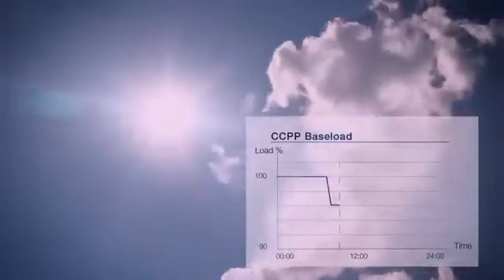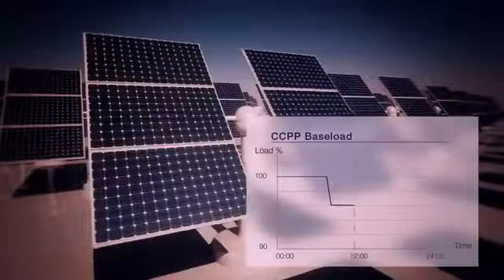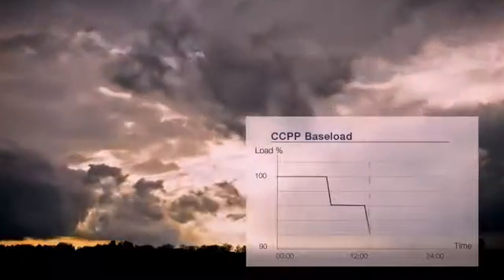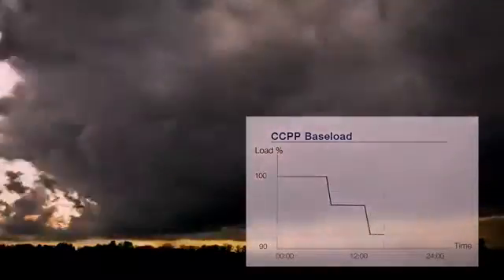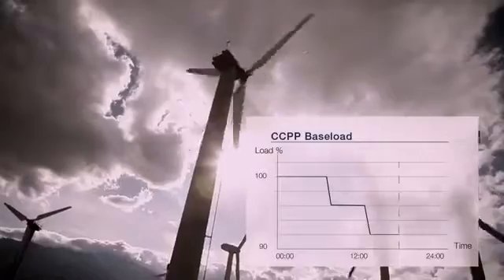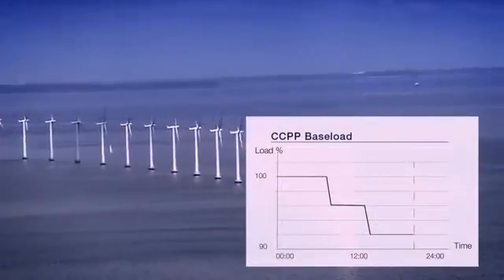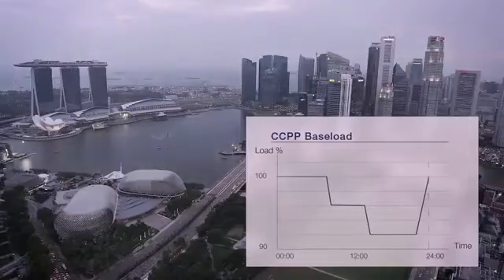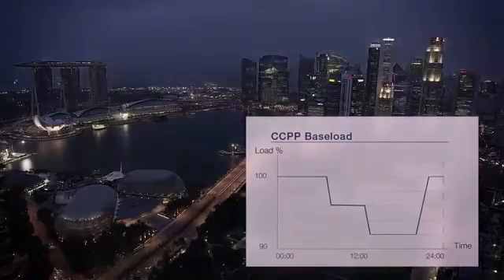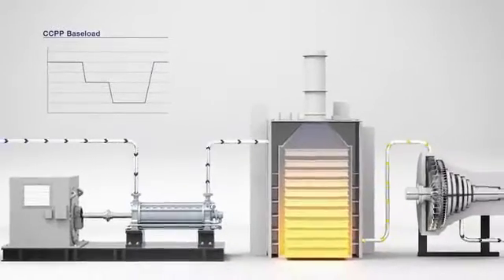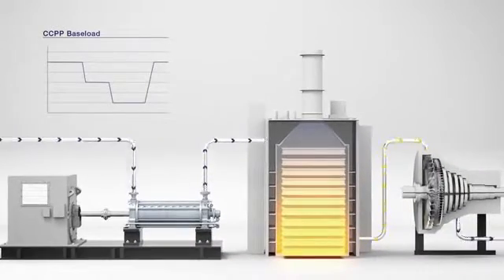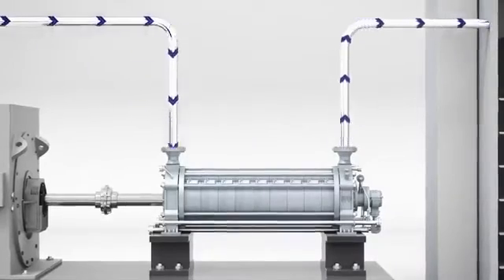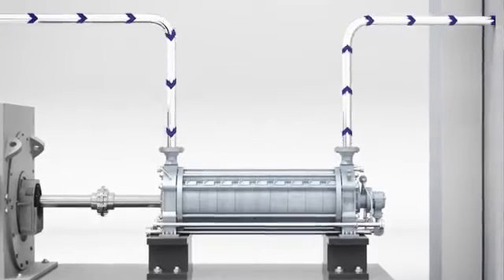Experience has shown that the conditions and requirements for modern combined cycle power plants have changed. Many power plants that were originally designed as baseload stations are later operated under partial load, because they must be able to balance out the fluctuations caused by renewable energy sources. This flexibility will become more and more important as time passes. The flow volume is varied in the boiler feed water supply circuit in order to meet changing energy needs. There are currently 3 ways of doing this in practice.